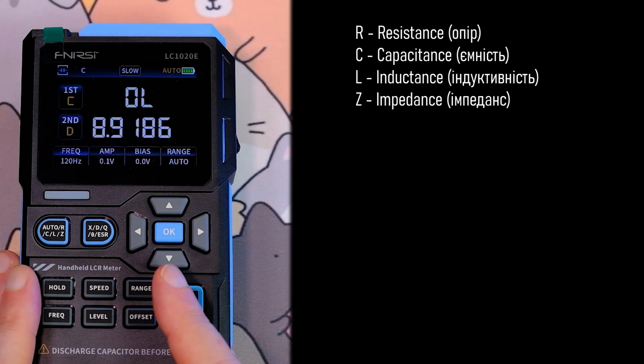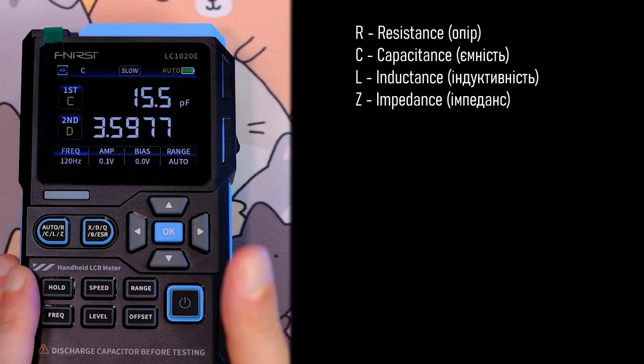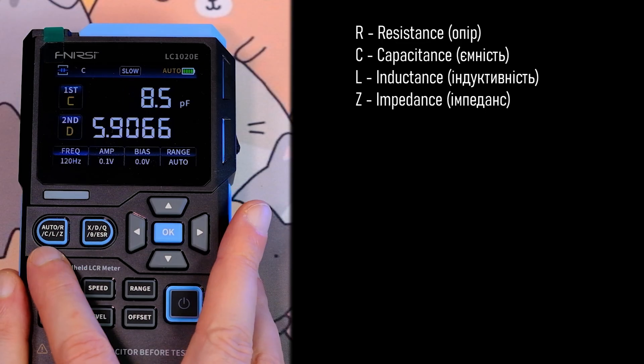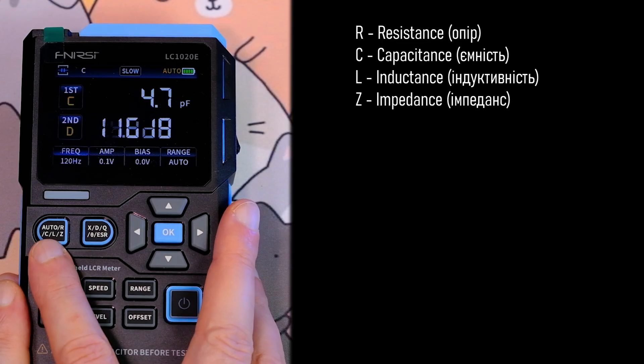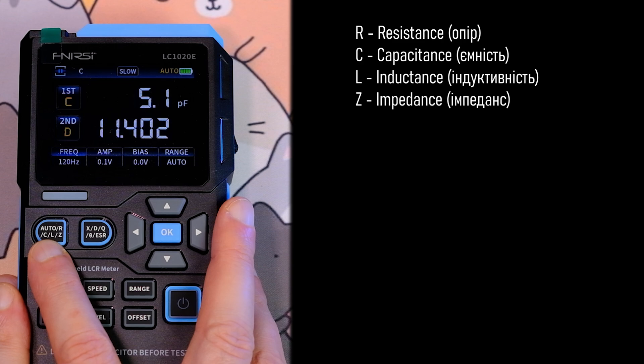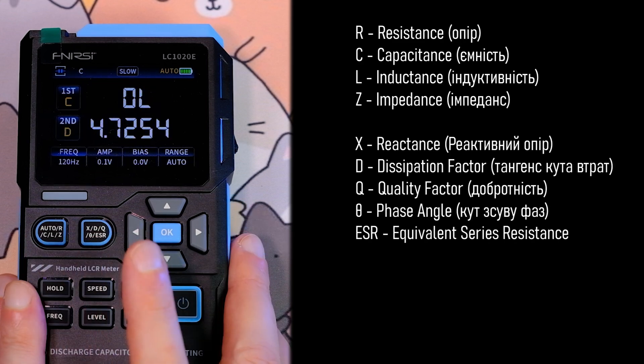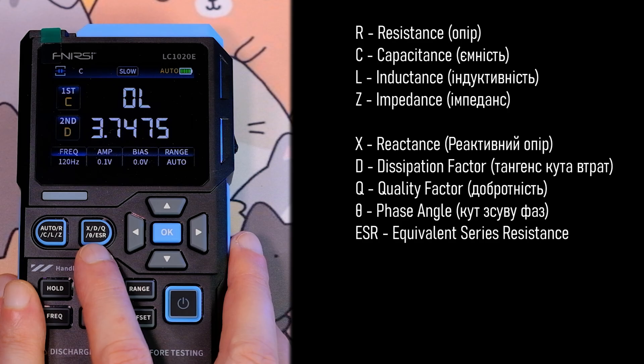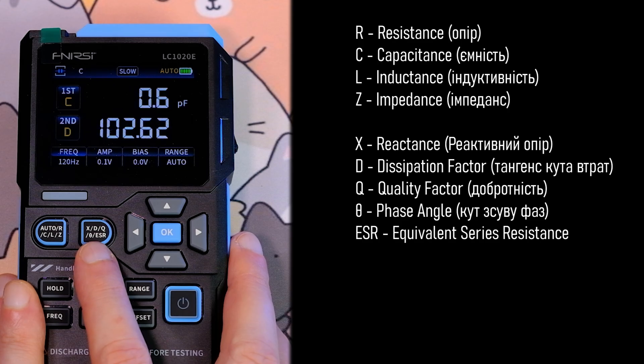The instrument can measure four main parameters and five secondary parameters. Main parameters: resistance, capacitance, inductance, and impedance. Secondary: reactance, loss tangent or dissipation factor, quality factor Q, phase angle theta, and ESR equivalent series resistance.